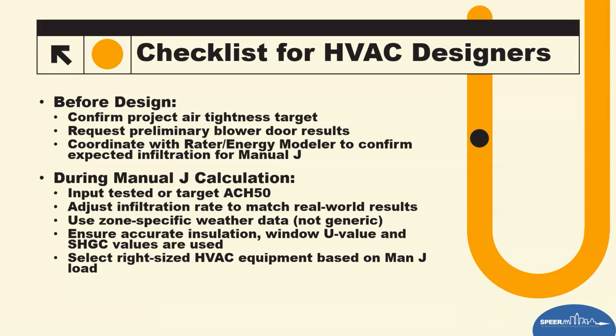So before the design, they're actually confirming the project airtightness target. In other words, what climate zone am I in? What city am I in? What's the requirement? Do I need to hit 4 ACH? Do I need to hit 5? Do I need to hit 3? So you just say, well, what's my target? Let's just say it's going to be 4. And so you're in the North Central Texas COG area. You're using the COG amendments for the 2021, and you're getting 4 ACH.